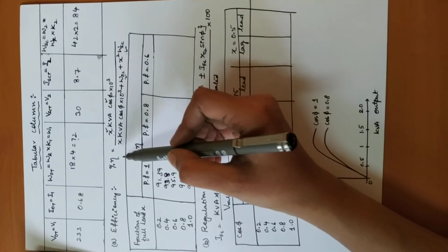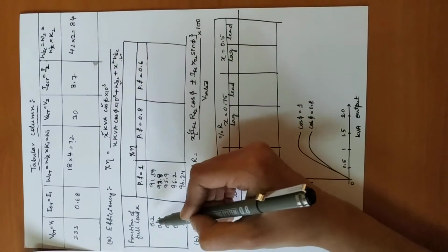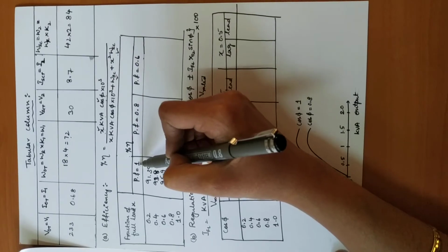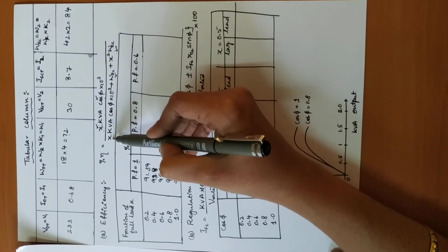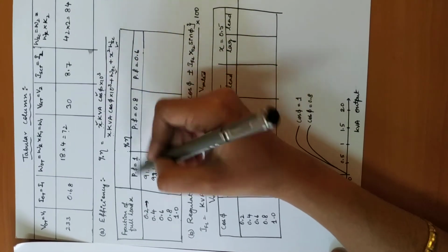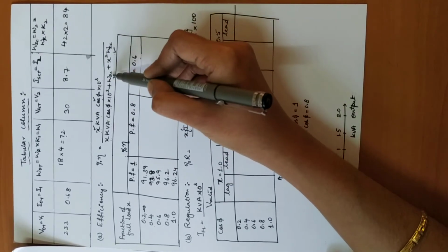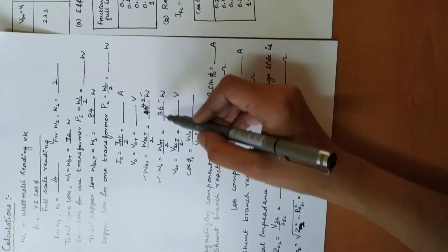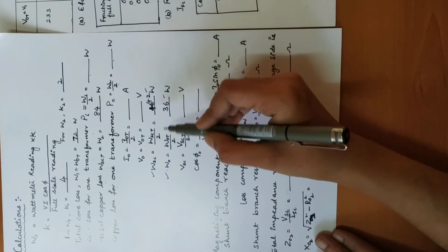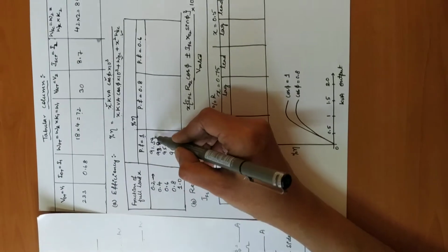to calculate that efficiency, just now we had refreshed the formula. So here for x we are going to substitute 0.2, kVA as 2, then cos phi we will take for the first column, that is 1, into 10 power of 3, divided by 0.2, so we are calculating for this part, that is 0.2, multiplied by 2 into cos phi is 1, and W naught C, you can consider here we have to take half of the value you had got for the total transformer, that is 36, plus x square, meaning the fraction of load 0.2 square, multiplied by 42. It results in 91.389%.